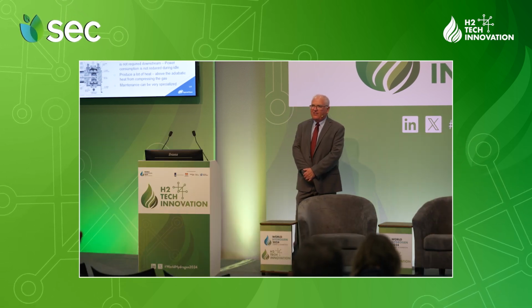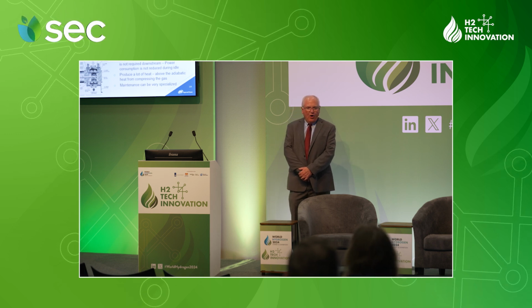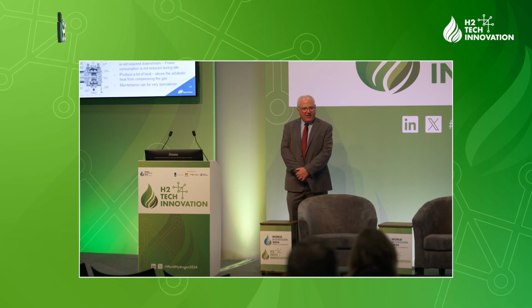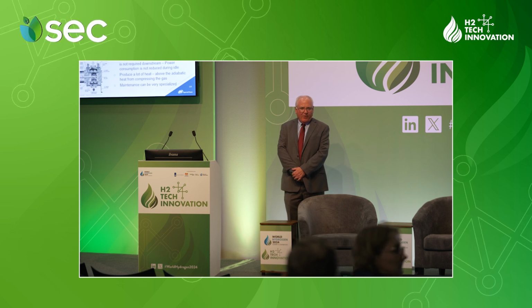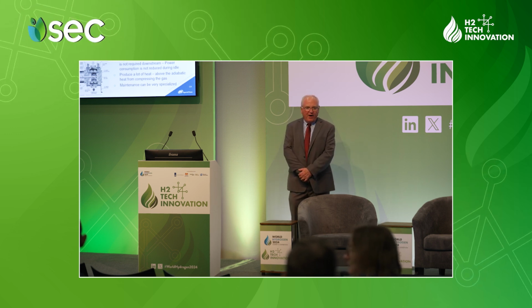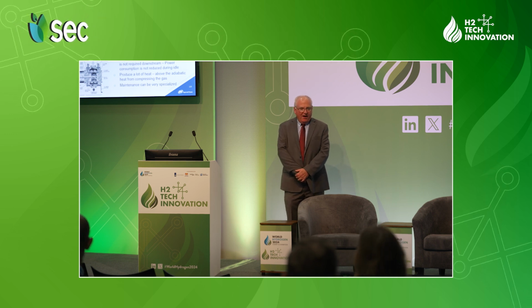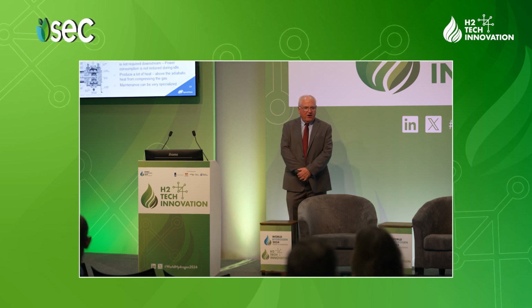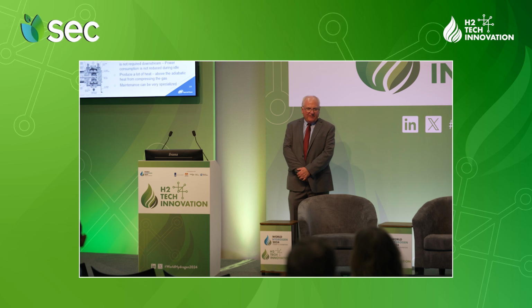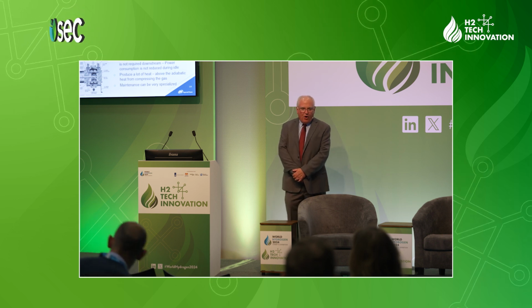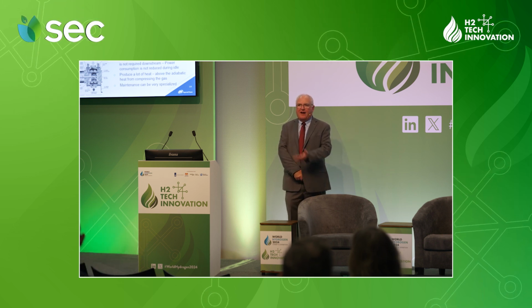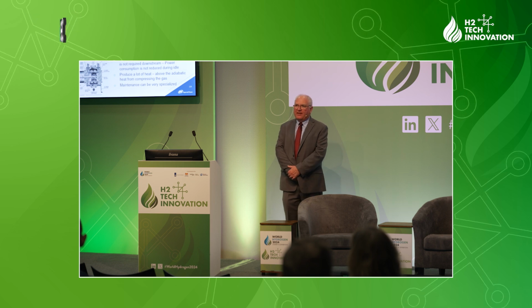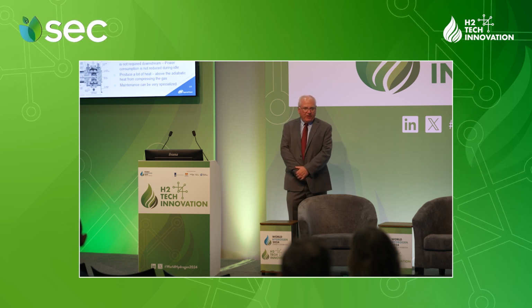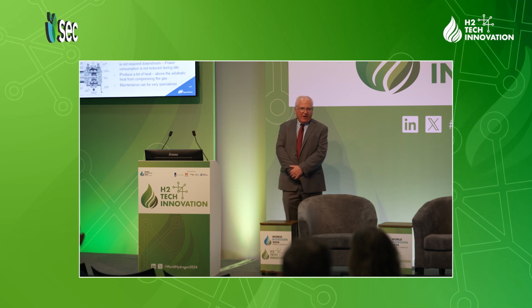Some of the disadvantages: they tend to have a very large footprint. Because of the large unswept volume, they require lower gas compression ratios, which means more stages of compression required. They can be noisy. They also cannot be started under load. They have to be unloaded before they can be started. And they're typically designed for a very narrow supply pressure for the gas coming into it. So you have to define a pretty narrow inlet pressure when you're selecting a compressor.